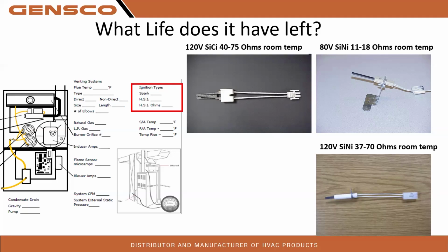especially if we're having an issue, some of the S9V2s can throw a code for an igniter problem. So if we know the ohms of the igniter, or what it should be, we can simply go, okay, is this a control board problem or igniter? Ohm it out. Let's say the 120 volt reads 40, it's a board problem, right? Something going on with the board. So this is really good data to digest as well.